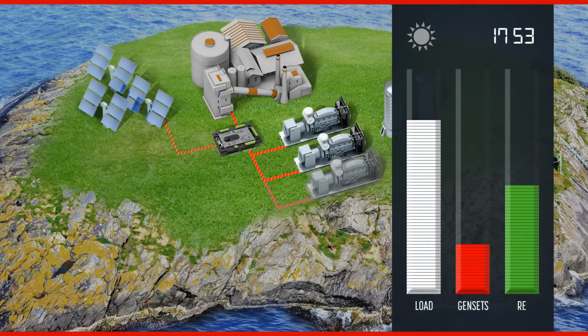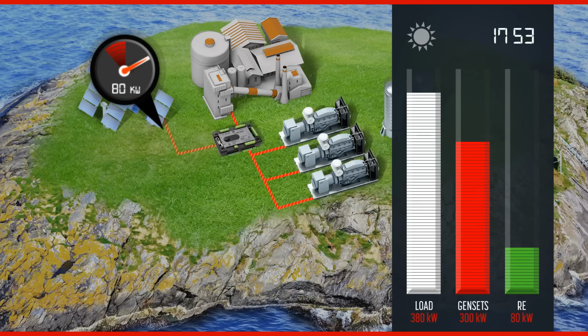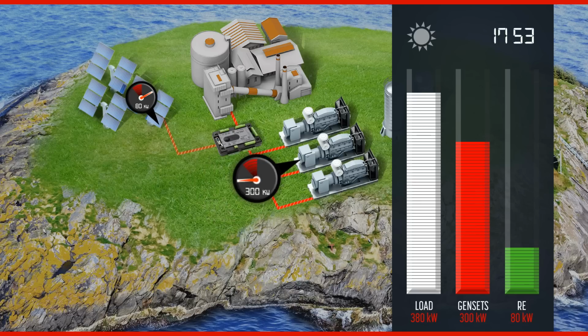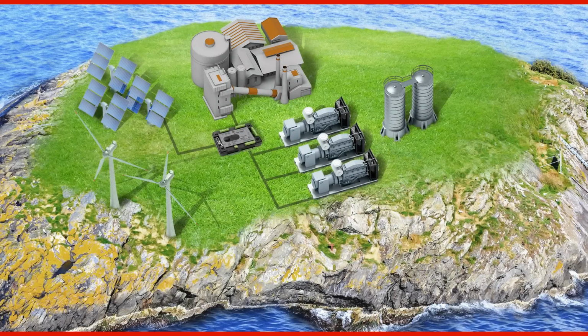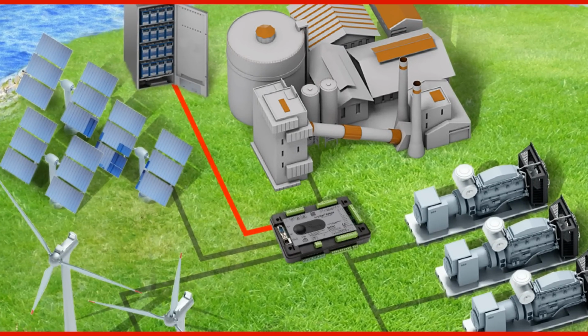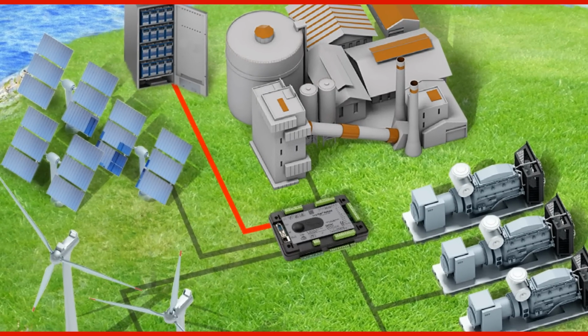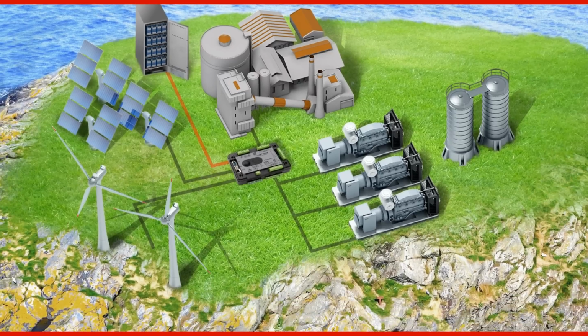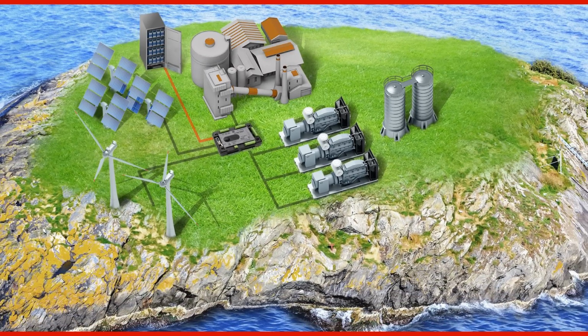Typically, during the afternoon, the PV output decreases, but the load increases. ComAp's controller will start, synchronize, and load more gensets to cover the increased load. This ensures a reliable power supply to all users connected to the power network. There are also hybrid systems which include batteries for storing surplus power generated by the renewable source. ComAp controllers are able to communicate with a battery management system to incorporate batteries into the hybrid system.